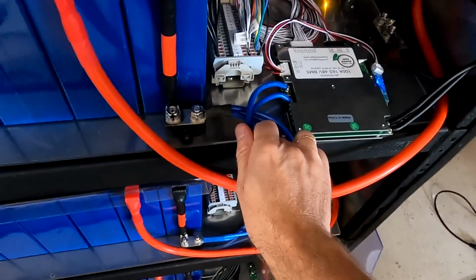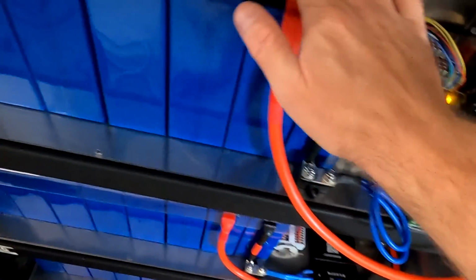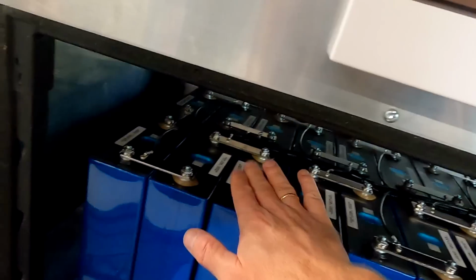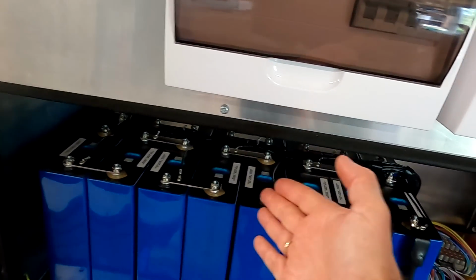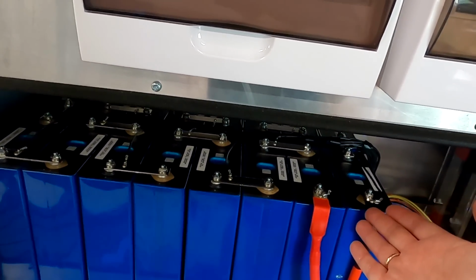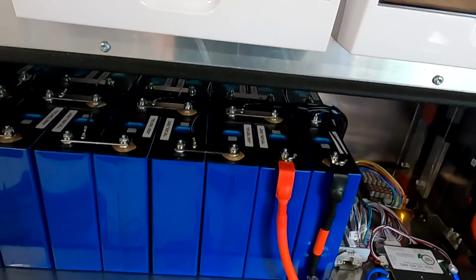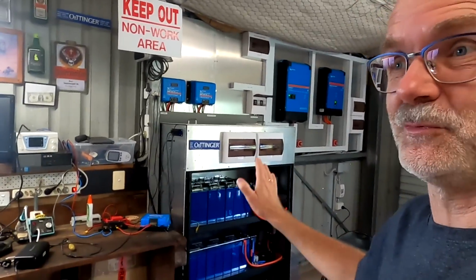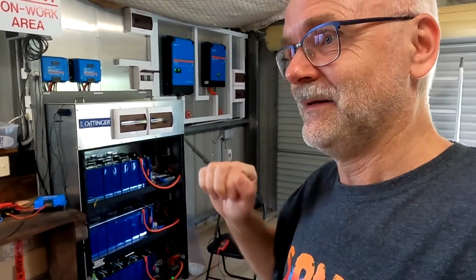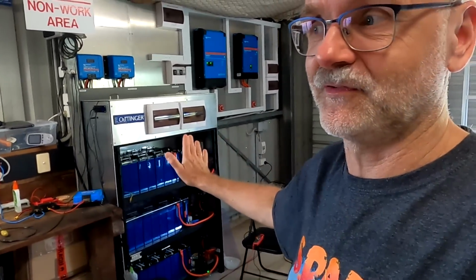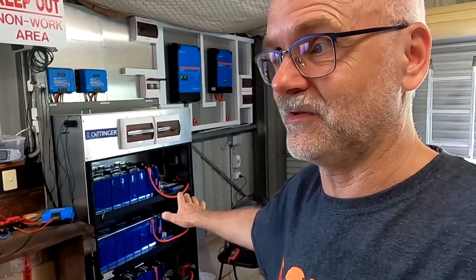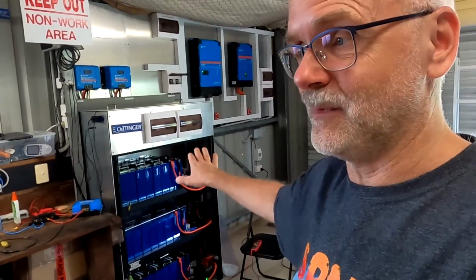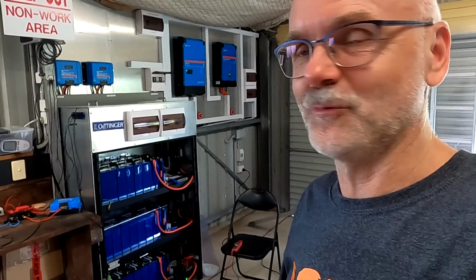So this will do nothing to the cables. There will be no heat up, nothing. The current is so small. I mean, we have pulled 230 amps from each battery bank here with no problem at all. So 40, that is nothing. Again, another test which I think needs to be done just to ensure everything is working as designed. They're all nicely calibrated and delivering roughly the same amount of energy now to the inverters. So great, this is out of the way as well.